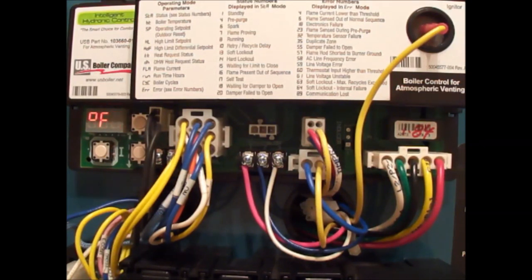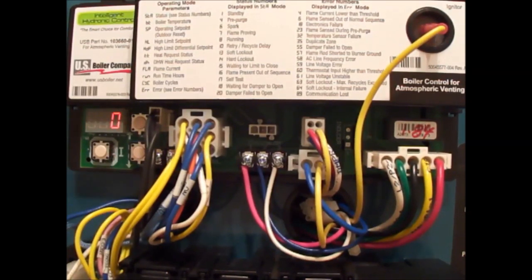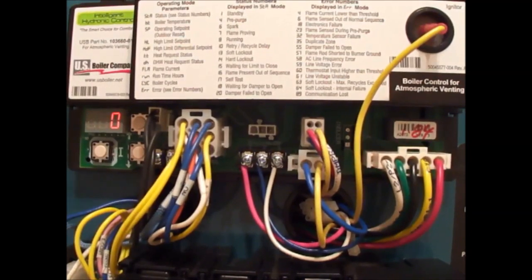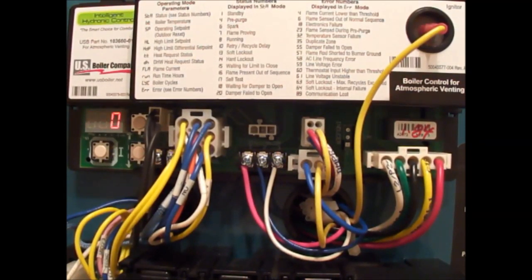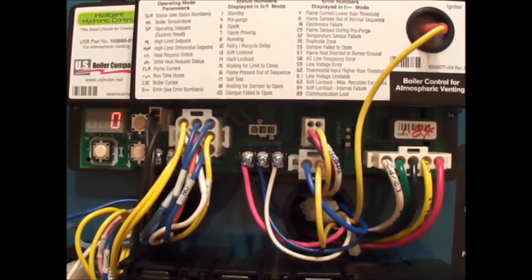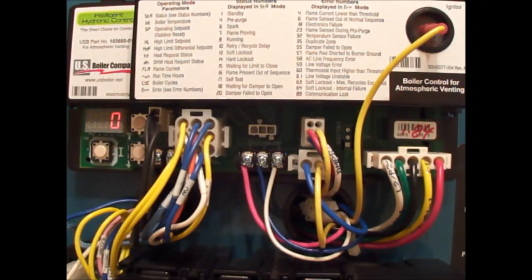We hit it again, we have OR. OR means pump overrun. This would be pump post purge. You created the heat in the boiler, thermostat satisfied. We can keep the circulator running a little bit longer to take that heat that you created and put it out in the house. This helps to save fuel.